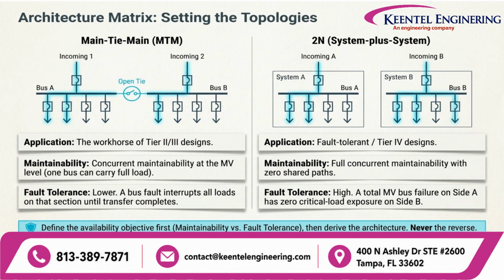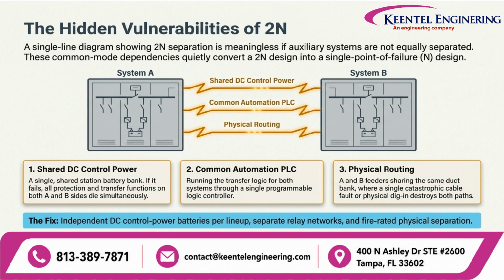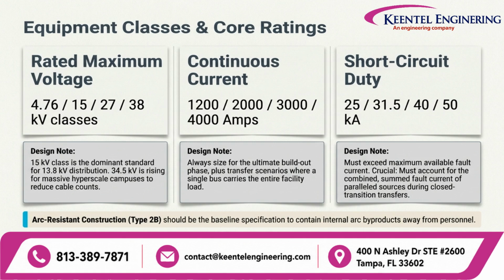When setting topologies, engineers often choose between main-tie-main or 2N architectures. The choice should always be driven by your specific availability objective, balancing maintainability against fault tolerance, rather than defaulting to a specific design habit. A 2N design is only effective if its auxiliary systems are also fully separated. Shared DC control power, common PLC logic, or unseparated physical routing can turn a theoretically redundant design into a single point of failure. Core ratings for switchgear must be carefully selected.